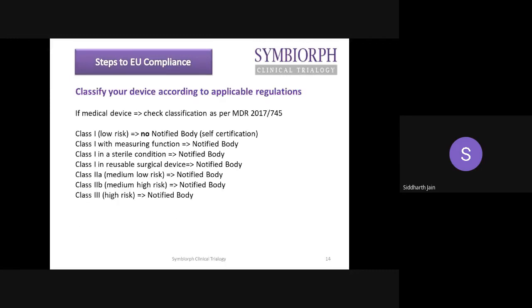Right. Next slide. Now, classify your devices according to the applicable regulations. As I already discussed, there are mainly three classes: 1, 2, and 3. But if you look at the regulations more in depth, class 1 is further divided into class 1 low risk. It means that all such devices will be self-certified. It means there is no requirement of an external notified body.